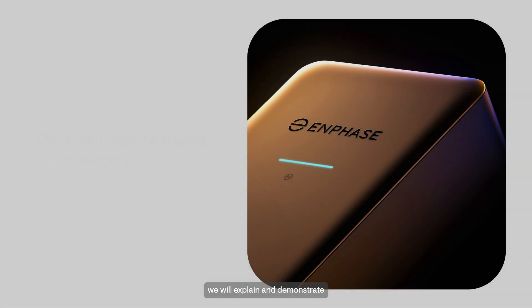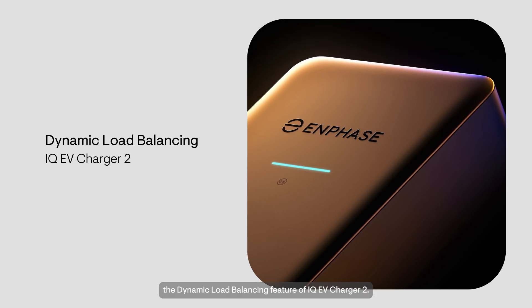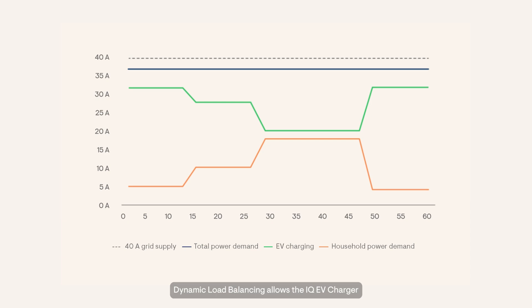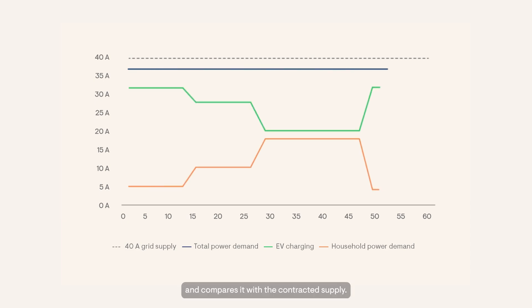In this video, we will explain and demonstrate the dynamic load balancing feature of IQ EV Charger 2. Dynamic load balancing allows the IQ EV Charger to adjust the EV charging power according to the household power demand. This ensures that the total home consumption does not exceed the contracted per-phase power or fuse rating, protecting the home and avoiding the need for expensive upgrades. The system monitors the total power demand of the home and compares it with the contracted supply.